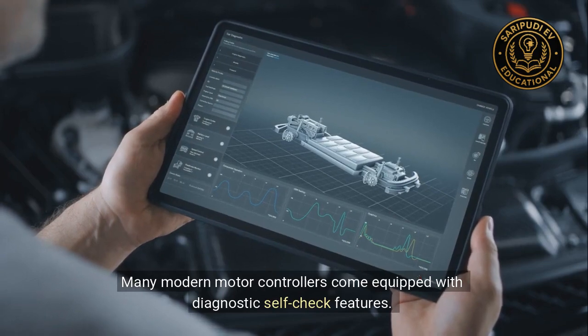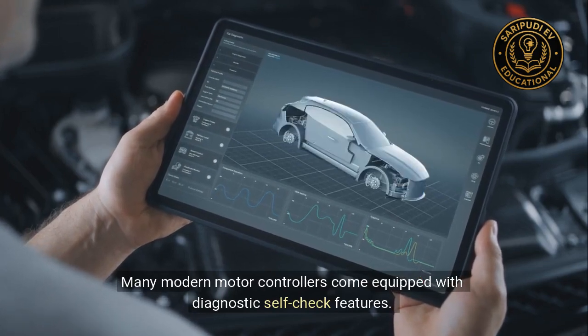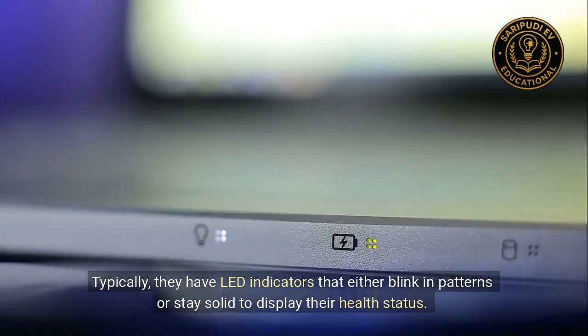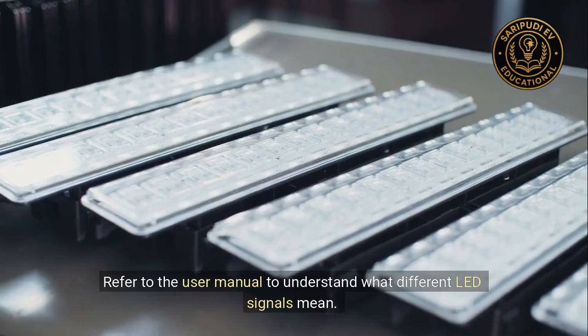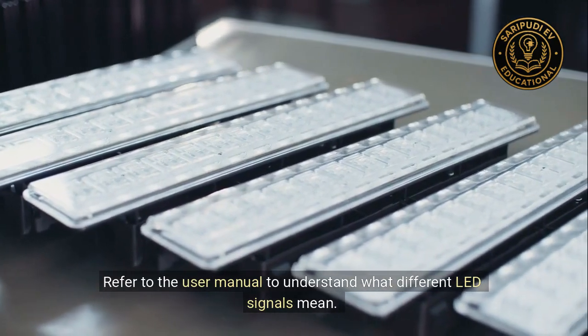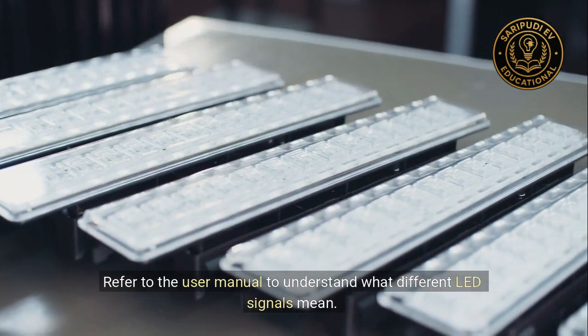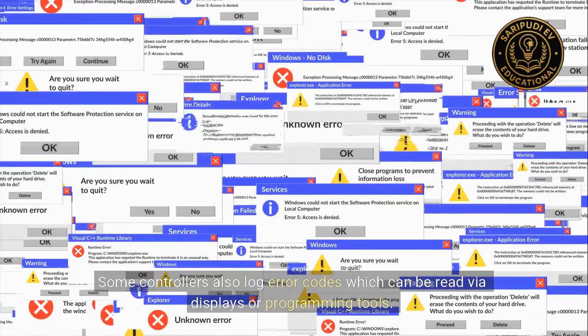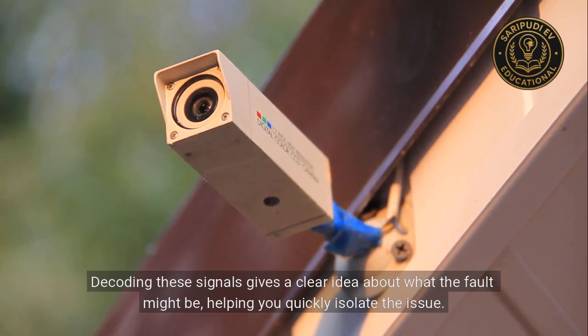3. Controller self-check. Many modern motor controllers come equipped with diagnostic self-check features. Typically, they have LED indicators that either blink in patterns or stay solid to display their health status. Refer to the user manual to understand what different LED signals mean. Some controllers also log error codes, which can be read via displays or programming tools. Decoding these signals gives a clear idea about what the fault might be, helping you quickly isolate the issue.